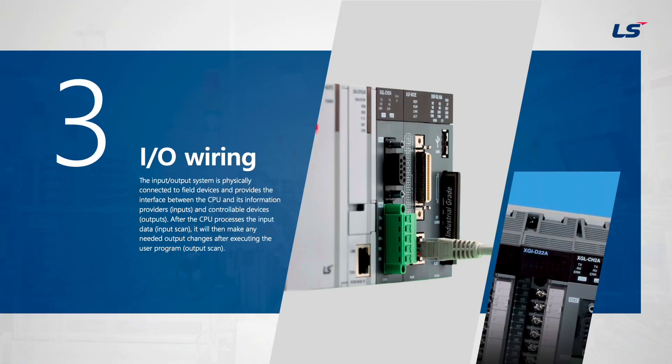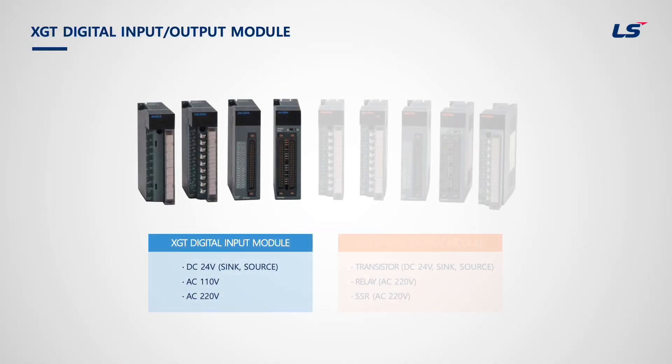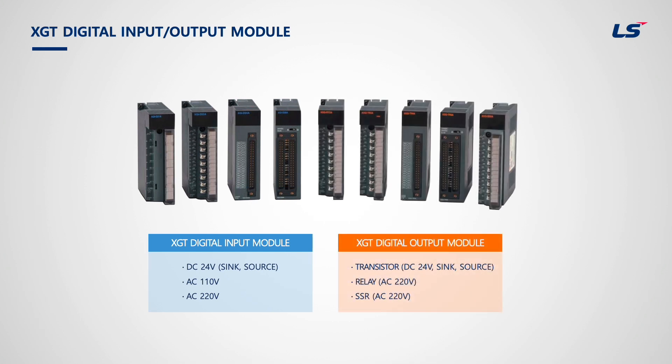Chapter 3 is about input-output wiring. These are digital input and output modules. On the left-hand side are digital input modules and on the right-hand side are digital output modules. Digital input modules use DC 24 voltage or AC 110/220 voltage. The DC type has both source and sink types, and some modules can be used as both sink and source.